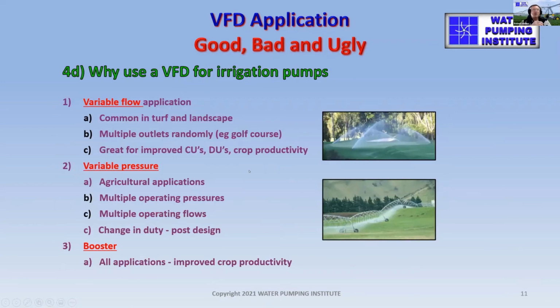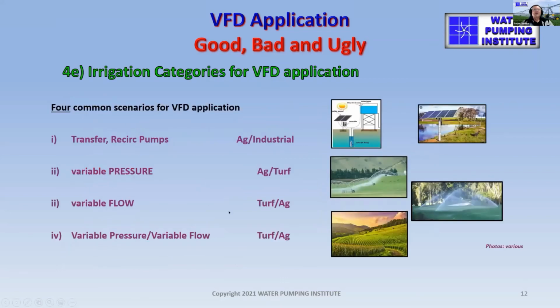Variable pressure, this is more ag, where you have the same flow, but you want to vary the pressure. You might want to change from one type of emitter to another, or you might have a variable elevation situation with a center pivot. And then there's, of course, the booster application. So we look at these four common scenarios: the transfer or reticulation pump, variable pressure in turf particularly, variable pressure in ag particularly, and variable flow in turf. Then you get the mixture of those two.